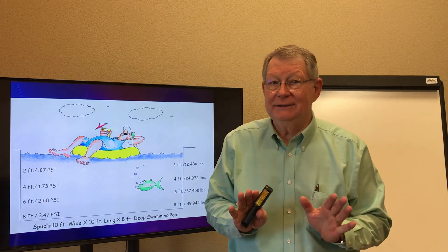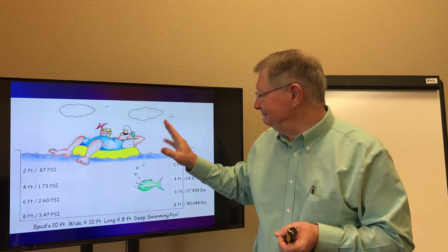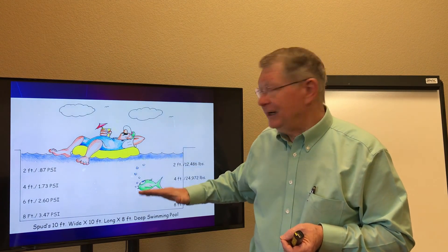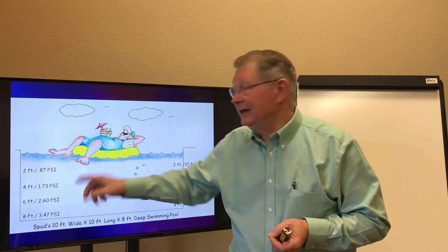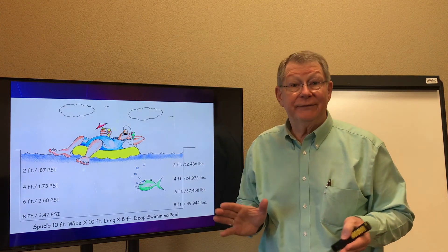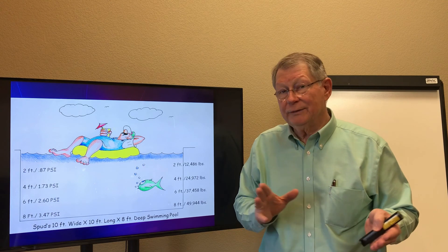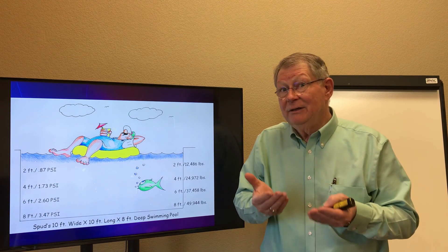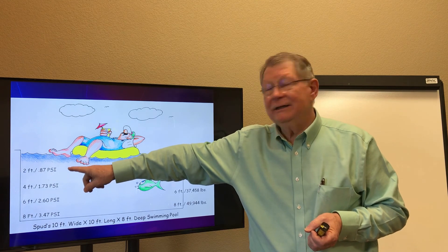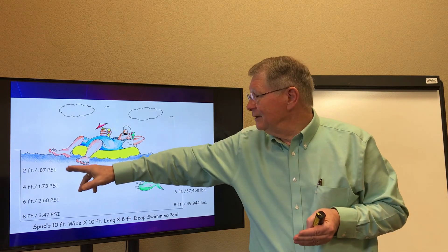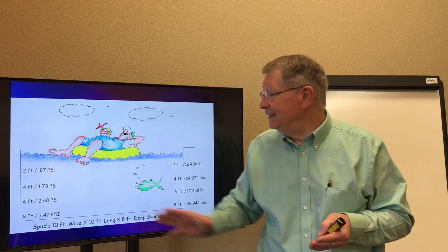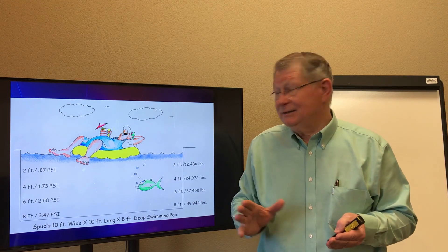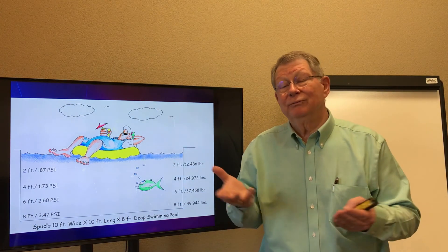To illustrate this, let's use a swimming pool and Spud the pump mechanic. He's in a 10 by 10 by 8 foot deep swimming pool. As we layer water on top of this pool, we find that the pounds per square inch increases. At two feet we have about 12,400 pounds of weight; at four feet, 24,900 pounds; and at eight feet, about 50,000 pounds. The PSI increases accordingly — starting at 0.87 PSI at two feet and reaching 3.47 PSI at the bottom. More water, more weight, more pounds per square inch.